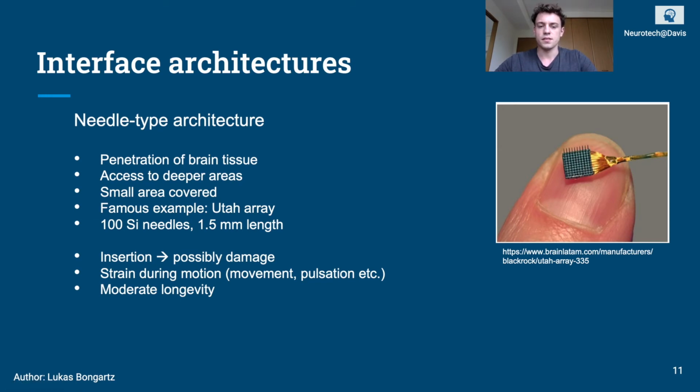And as this device is inserted directly in the brain tissue, it has, of course, the potential for damage of the tissue. And apart from this, an important aspect is that micromotions, so for instance, the pulsation of the brain around those stiff silicon needles, can induce inflammatory reactions and strain on the brain tissue. This again can then impair the device longevity.